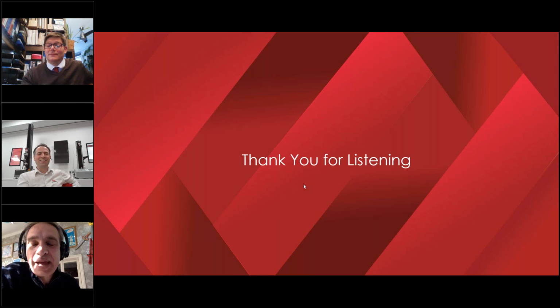I said we're quite happy to have another webinar, but just to address the question, they are different, but they are very similar in certain respects. So as long as you understand the nuances between the two techniques, then you can use either. But I think for someone that's never used potential drop before, we would always recommend DC. Matelect manufacture both AC and DC, so we've got no axe to grind. At the end of the day, we look at the application, we say what's more suitable.